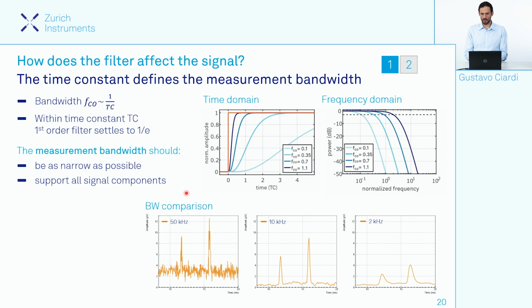Here on the top plots, we have both the time domain and frequency domain response of filters with different bandwidths. As we decrease the bandwidth of our filter, we are of course making the measurement bandwidth narrower. This means that we are letting through fewer and fewer frequency components, meaning that we are able to reject more noise. At the same time, though, the price to pay is that we need to wait longer for the filter to settle to the new value. I want to mention that this is a physical trade-off that one needs to make. It has nothing to do with the instrument. This is how the physics of the low-pass filter works.